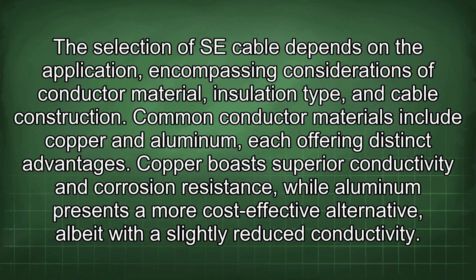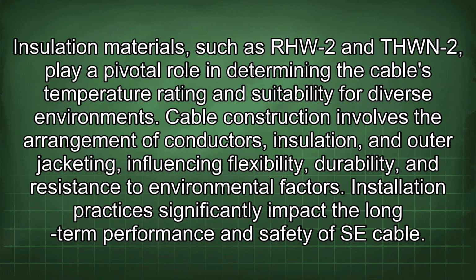The selection of SE cable depends on the application, encompassing considerations of conductor material, insulation type, and cable construction. Common conductor materials include copper and aluminum, each offering distinct advantages. Copper boasts superior conductivity and corrosion resistance, while aluminum presents a more cost-effective alternative, albeit with slightly reduced conductivity. Insulation materials such as RHW-2 and THWN-2 play a pivotal role in determining the cable's temperature rating and suitability for diverse environments. Cable construction involves the arrangement of conductors, insulation, and outer jacketing, influencing flexibility, durability, and resistance to environmental factors. Installation practices significantly impact the long-term performance and safety of SE cable.